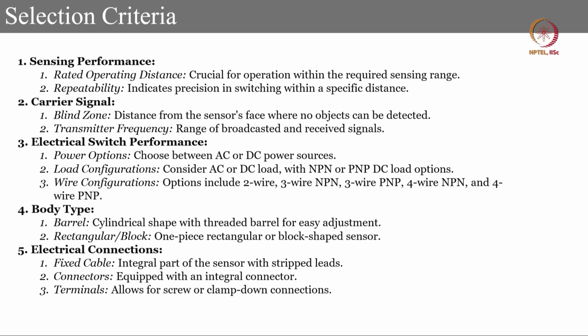For example, sensing properties, carrier signal, electrical switch performance, body type, electrical connections. So, what are these things? For sensing performance, we have to see the rated operating distance, how much the sensor can detect. Repeatability is how accurately it can detect. Repeatable results are there if you do measurements 10 times, what are the outputs for the same distance that we are measuring. Carrier signal is a blind zone distance from the sensor face where no objects can be detected. Transmitter frequency is the range of broadcasted and received signals.